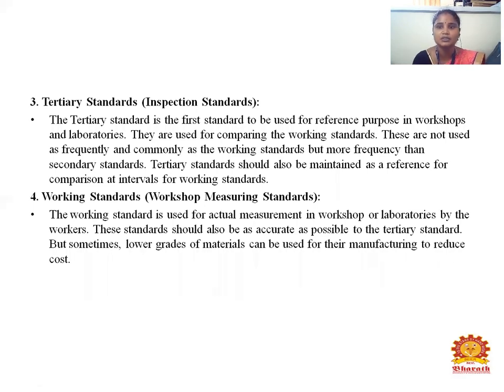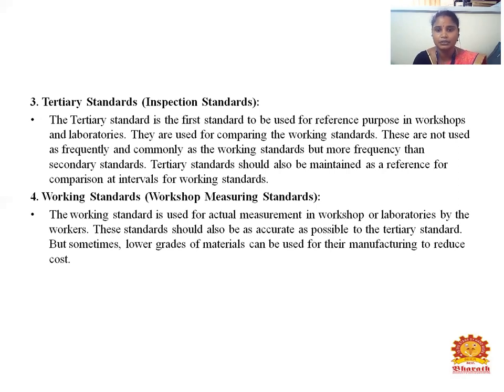The tertiary standard, also known as inspection standards, is the first standard to be used for reference purposes in workshops and laboratories. They are used for comparing working standards, but are used less frequently than working standards and more frequently than secondary standards. Working standards, also known as workshop measuring standards, are used for actual measurement in workshops or laboratories by workers. These should be as accurate as possible relative to the tertiary standard, though lower grades of material can sometimes be used to reduce cost.